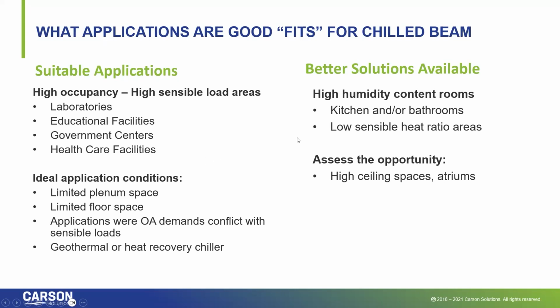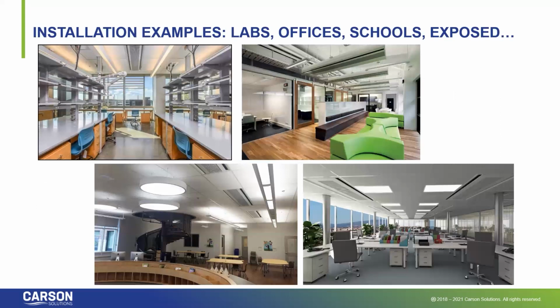What might not be good solutions? Those areas where high humidity resides, or kitchens or bathrooms or cafeterias. And then maybe even high ceiling heights might not be a good solution as well. And what you see on the screen is suitable installations. Laboratories are a very good fit. Here you have an office space with exposed chill beam. And then here on the bottom, you have an educational facility and an office space being served by very traditional in-ceiling chilled beams.